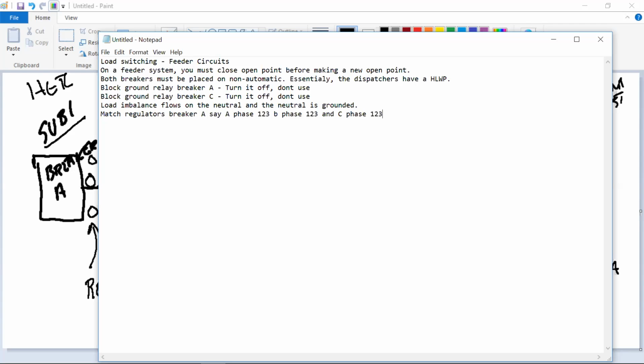Exactly. Match breaker C regulators, A phase 1, 2, 3, B phase 1, 2, 3, C phase 1, 2, 3. Okay. So now the voltages at both substations' regulators are matched to each other. It's not going to be exact, like I said, and you want to keep it within a volt range.